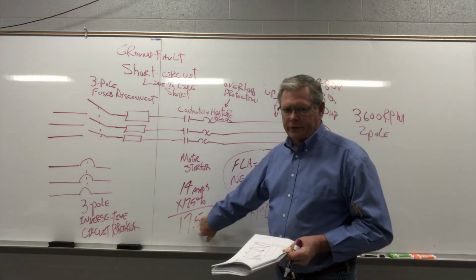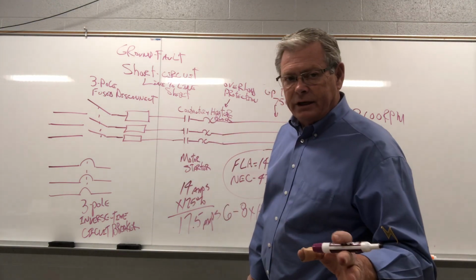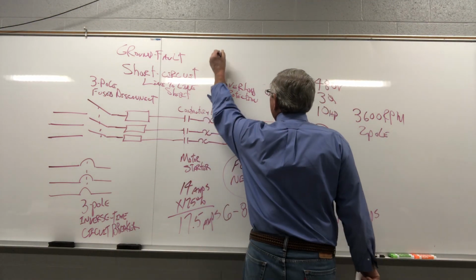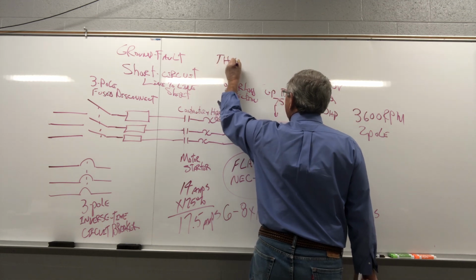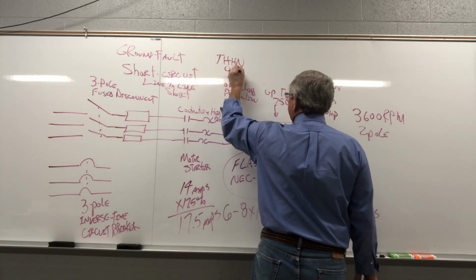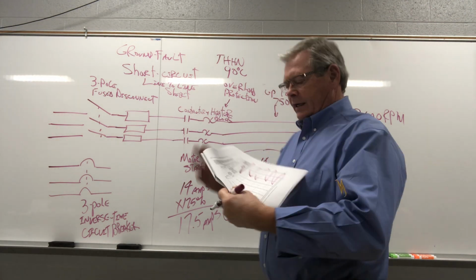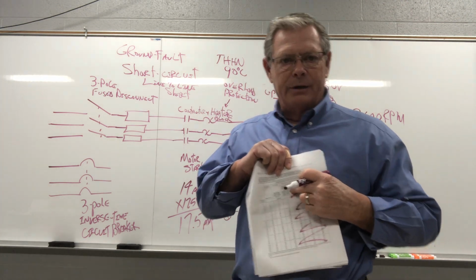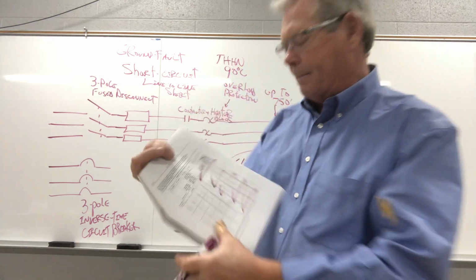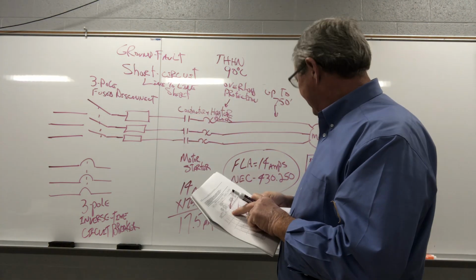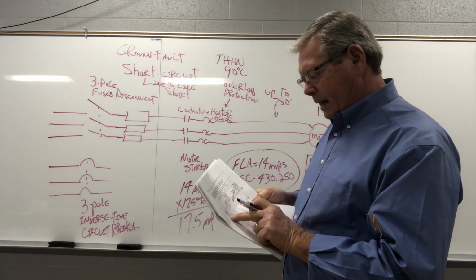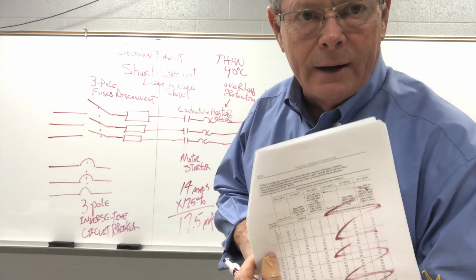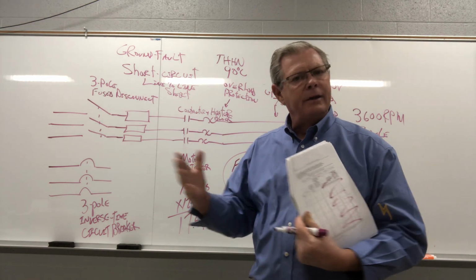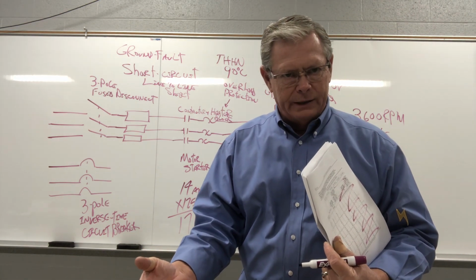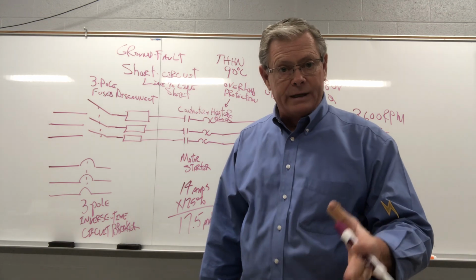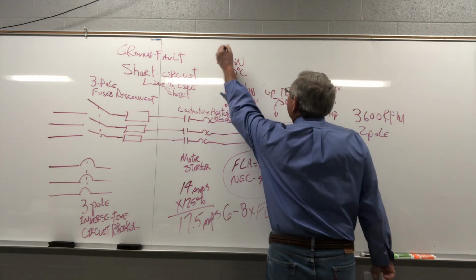So we're going to look down through there, and we're going to pick the kind of insulation we're going to use. Most of the time, we're using THHN. And that is 90 degrees C wire. So THHN is in this column here, third one over, okay? Now we're going to go down till we find at least 17.5 amps. And when we look over there, it says 16 gauge wire. But what did the other page say? The other page says we can't pull in anything smaller than 14. So we got to automatically go to 14 gauge wire, okay? So, number 14.